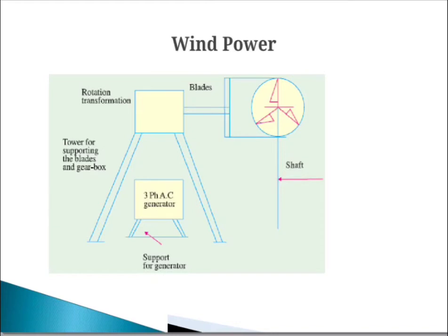Then the turbine controller is computer based or PLC based and controls the entire turbine. It starts and stops the turbine and runs self diagnostics in case of any error in the turbine. Next is the anemometer. It measures the wind speed and passes the speed information to the PLC to control the turbine power. Then the wind vane sends the direction of the wind and passes the direction to the PLC.